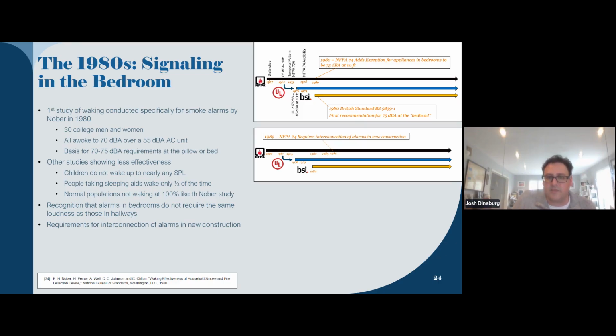One interesting thing that did get added here in 1980: at the time, we were really only putting alarms in hallways - that's the only place they were required. But NFPA 74 did recognize that if it's going in the bedroom, it doesn't really have to get through a door. So there was an allowance made to let the devices be 75 instead of 85 dBA - be a little quieter. It's going right in the bedroom, this should still be fine.